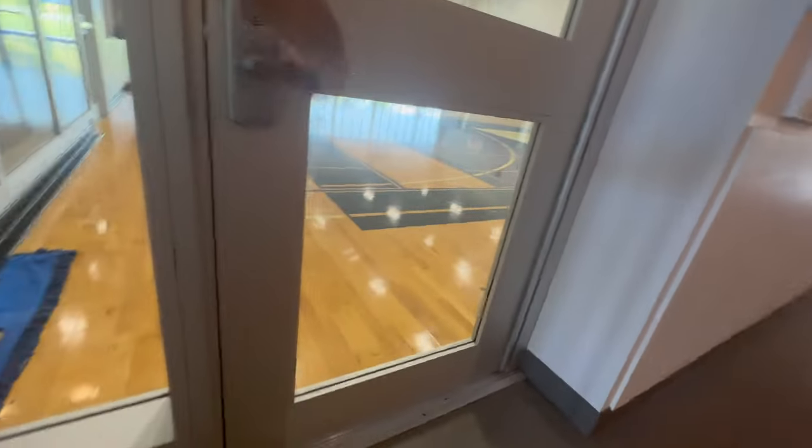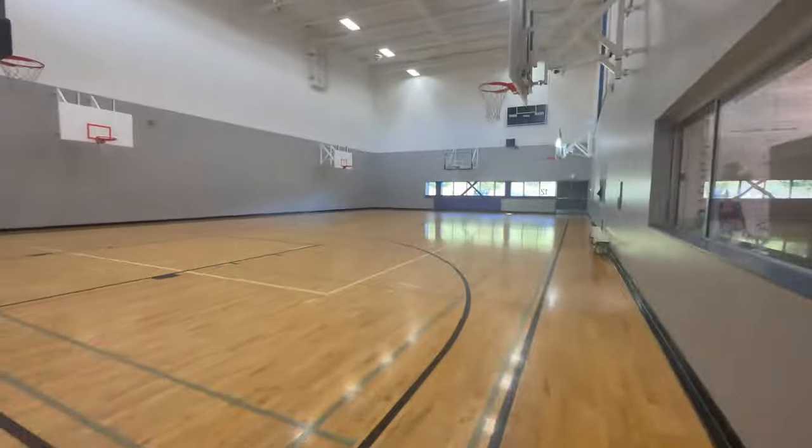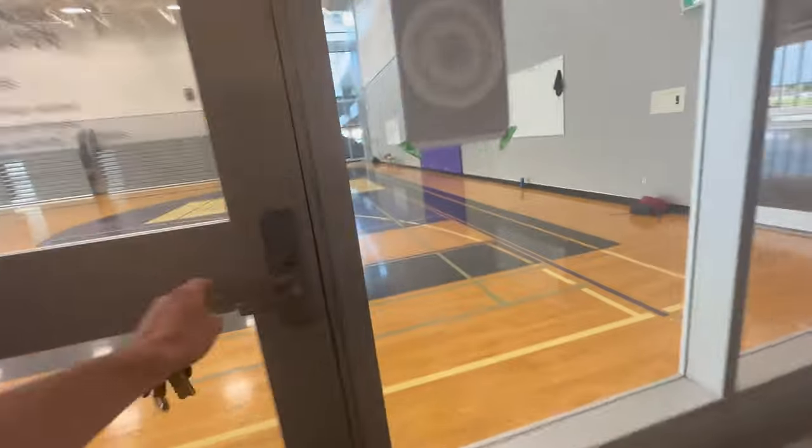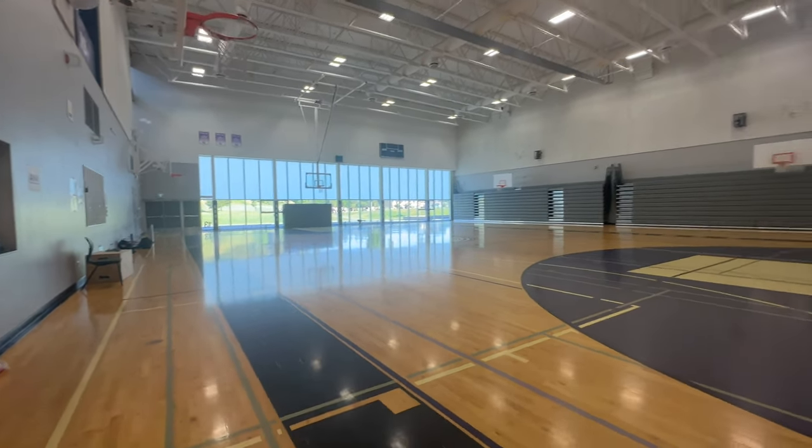In the turf gym, one of those horn strobes somehow is doing continuous. It's not doing temporal anymore. It's just... Oh, you sound weird. Yeah, because it's not synchronized. It's almost like it's straight through because they're not in sync. So nothing's in sync. Look at the shop while nobody's in there. Yeah, I'm telling you, though, that one is on continuous for sure. I went right beside it. See, these two in here are synchronized.